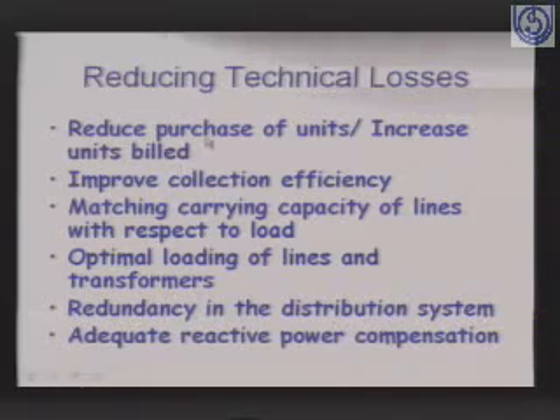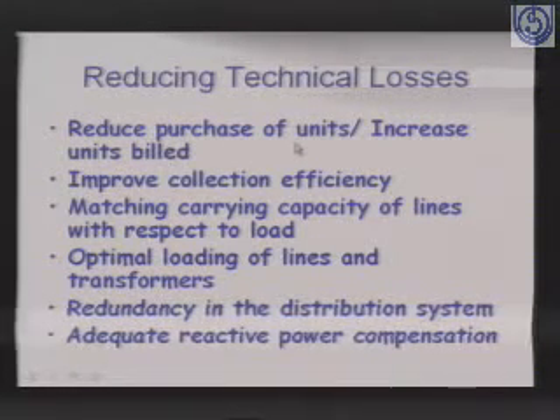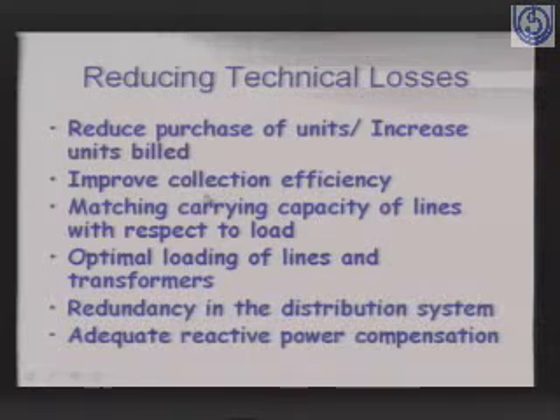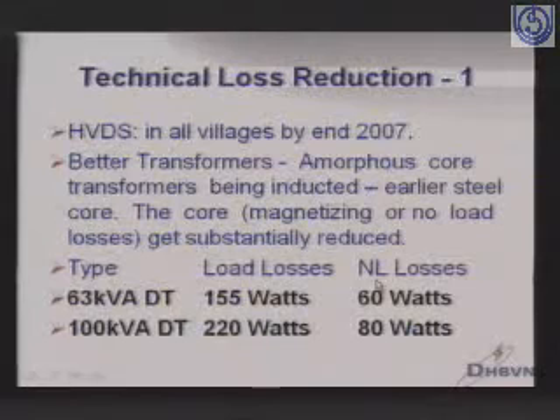To reduce technical losses, the aim is to reduce purchase of units or increase units billed, improve collection efficiency, match carrying capacity of lines with load, ensure optimal loading of lines and transformers, add redundancy in the distribution system, and provide adequate reactive power compensation through power factor capacitors.